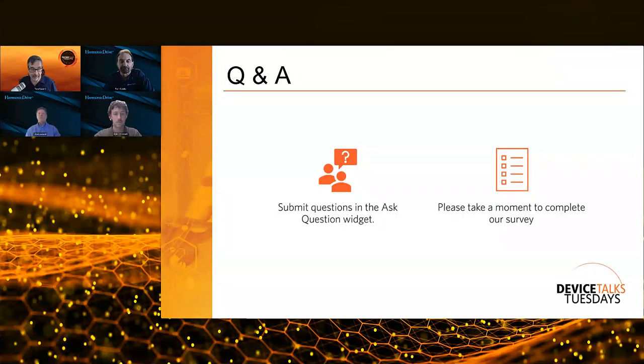I'll take a stab at that. Basically, the key is to treat lubrication as a life-limiting design element, not as an afterthought, especially in these sealed medical environments we were just speaking about. Because of the highly sealed medical situation, there are very limited relubrication options. The good news is we offer various types of harmonic drive grease suitable for all types of temperature conditions, duty cycles, torque, and speeds. We have our line of standard lubrication as well as extreme environmental conditions. So generally speaking, for most applications, our grease is meant to not need relubrication inside the gear train.